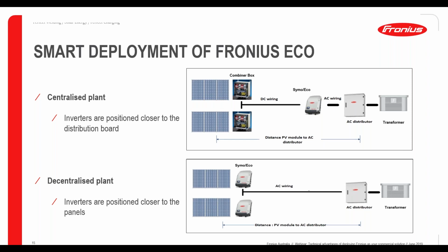Thanks, Timmy. So there's probably two main priorities in the way that we work out the location of the inverters. The first one would be a centralized plant, whereby all of the fusing and combining of the strings would be done prior to the connection on the DC side to the inverters. And typically the inverters are going to be positioned, as it says there, at a centralized point that's typically right next to where the AC distribution happens.